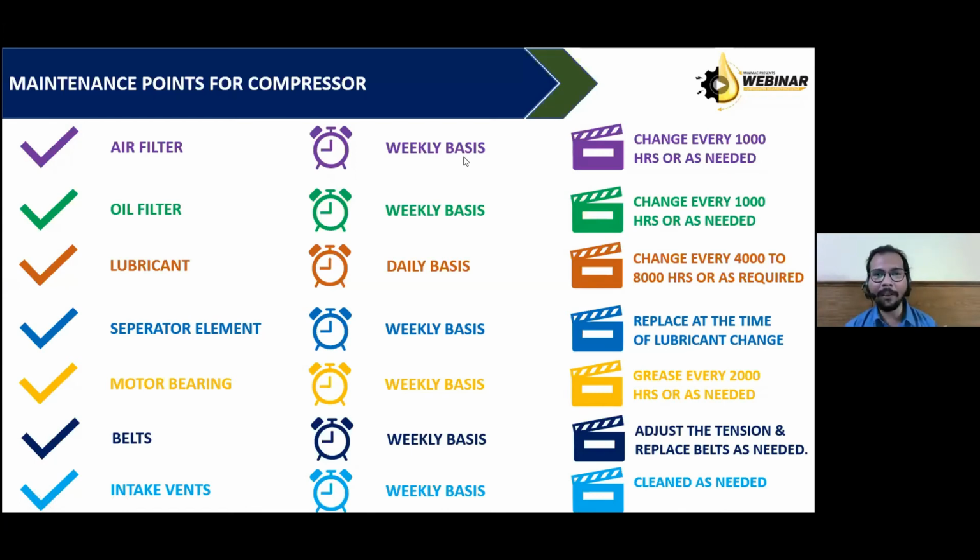Suppose we went and checked the lubricant level, then what should be the next step? It should be predefined. If the lubrication level is at normal level, shall we go to above normal, or do we have to wait for the low or low-low level? That should be predefined. So with every checkpoint, we should have a written document, and it should be common to all field operators or inspection engineers. So everyone will have the same platform to check and to take decisions.